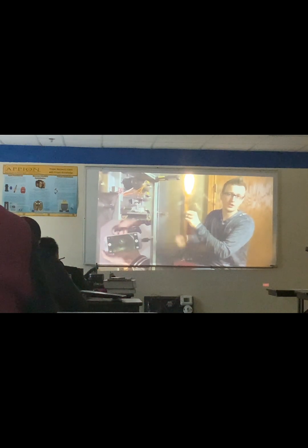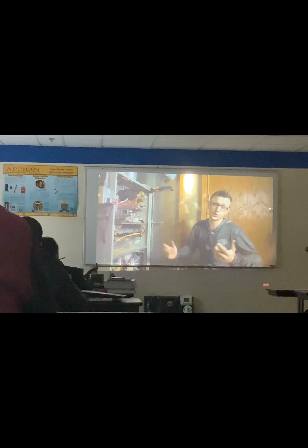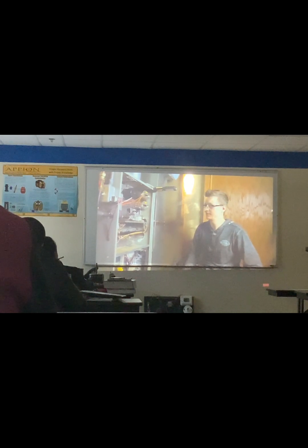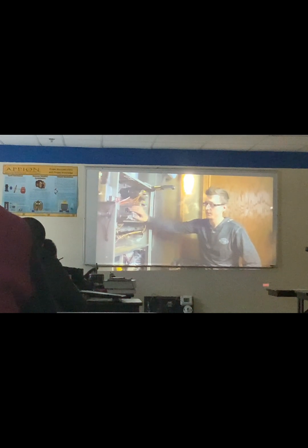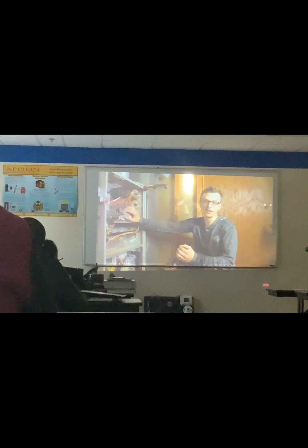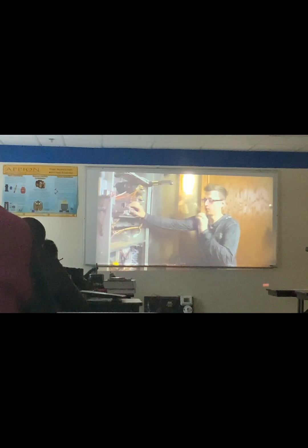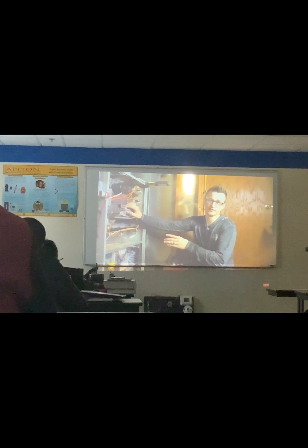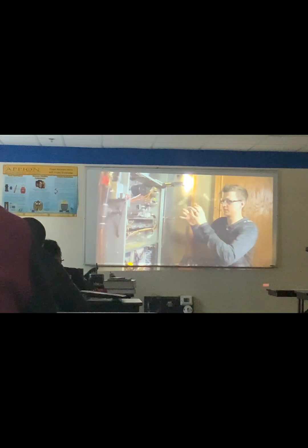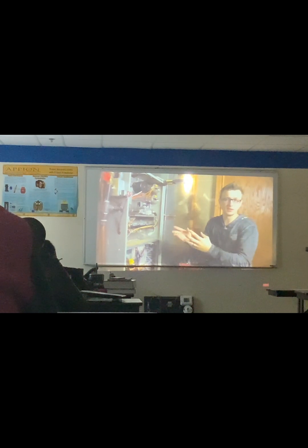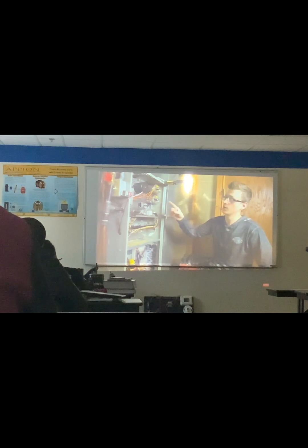There you are. You can also sneak in there and try to see where the cracks are. Long story short, the American Gas Association states that by code, if there is a crack or a hole in your heat exchanger, the heat exchanger or the whole furnace must be replaced. And the reason that's so important is because the heat exchanger is the thing that keeps all the combustion fumes out of your house supply air.